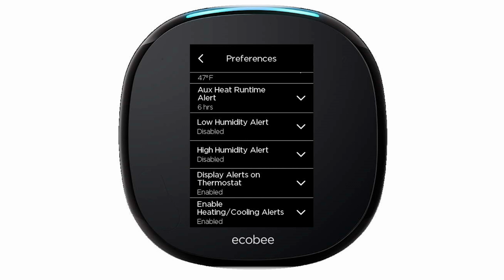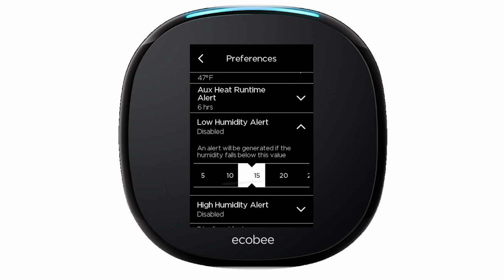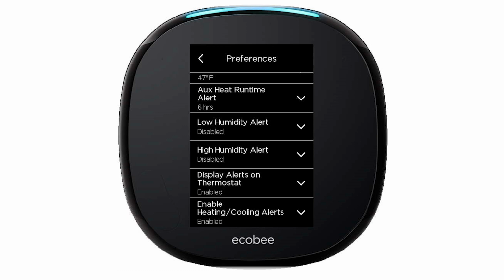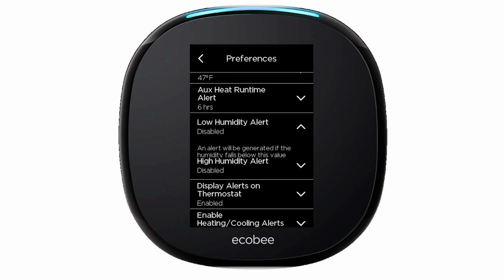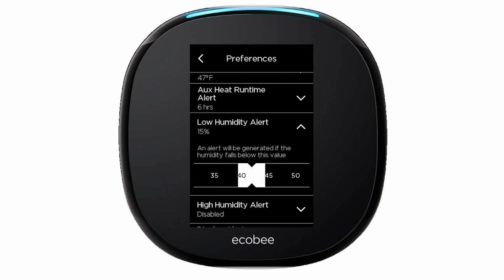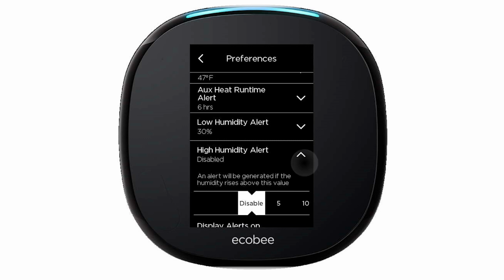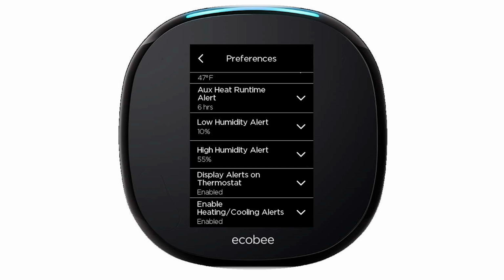So with humidity, you've got the same preferences. You can turn that off. You can adjust that low humidity, high humidity. We would probably recommend somewhere around 30% for your lower end, higher end somewhere around 55. When we reach the 60% humidity level, that's when mold can begin to grow. So something to keep in mind, adjust these.